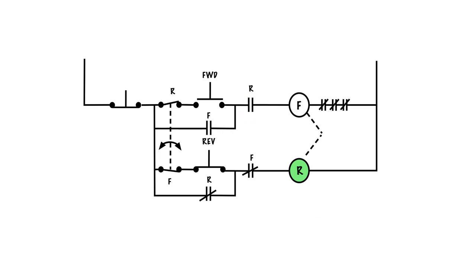I let go of the reverse button, it's being held in by itself with these R contacts, it's spinning in reverse. You notice up here my zero speed switch has opened up this side because of the centrifugal force which is opening up the reverse. I can sit here and hit forward, power is not going to get through, it's being held out anyways by these interlocks but there's no way for forward to become energized.